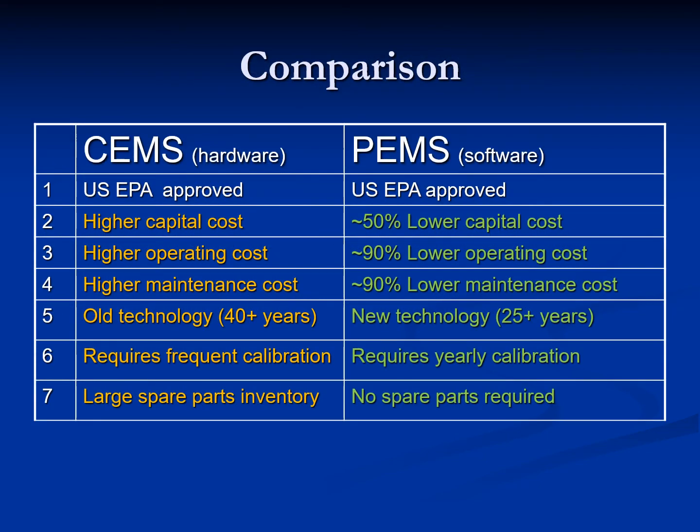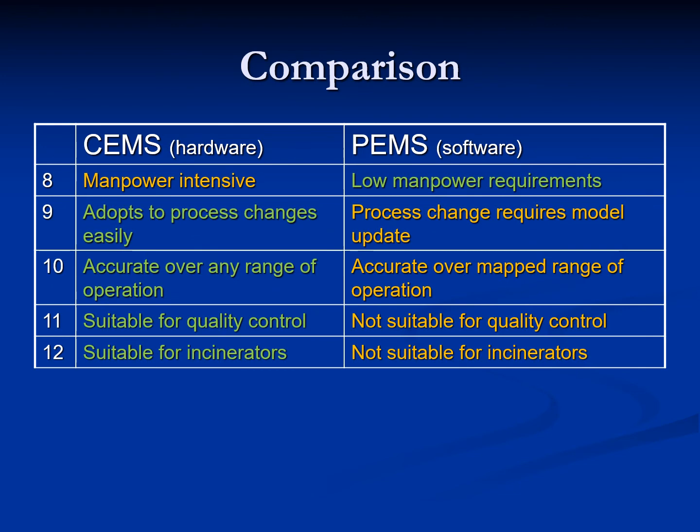Both the CEMS and PEMS have their own strengths. The PEMS has the following advantages: it is up to 50% lower in capital cost, up to 90% lower in operating and maintenance cost, it's a newer technology, requires only yearly calibration, and no spare parts are required. The hardware CEMS has the following advantages over PEMS: it adapts to process changes easily, is accurate over any range of operation, is suitable for quality control, and is suitable for incinerators.